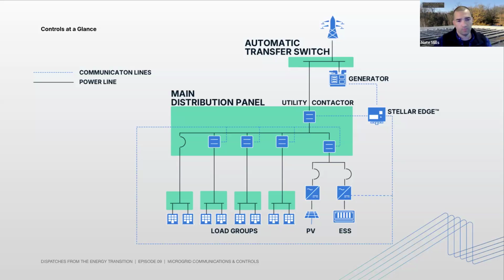Same, right? We have to find out from the client what they really need, because it may be that we need the dental suite for sure, and also the elevator, and then, oh yeah, if we don't keep the IT system up, we can't retrieve anybody's records. So we need those three things. Part of our job is to go find where those are in the building electrically and make sure they're all brought together in a way that we can support them all. So either that means rewiring some components to a critical loads panel designated for that purpose, or supporting multiple panels.